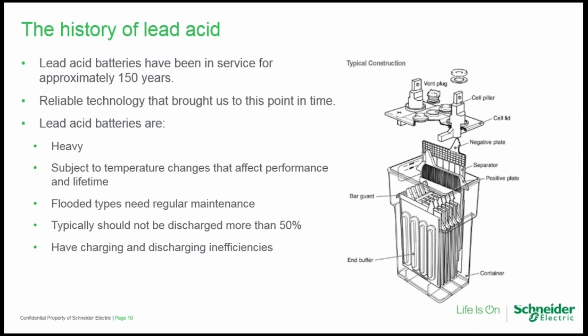However, they're heavy. They are dependent on temperature compensation to provide the same level of charge. So in colder environments, current flow is impeded. Therefore, a higher voltage needs to be targeted to obtain the same state of charge. And then, of course, in warmer climates, the battery voltage has to be decreased to prevent overcharging.